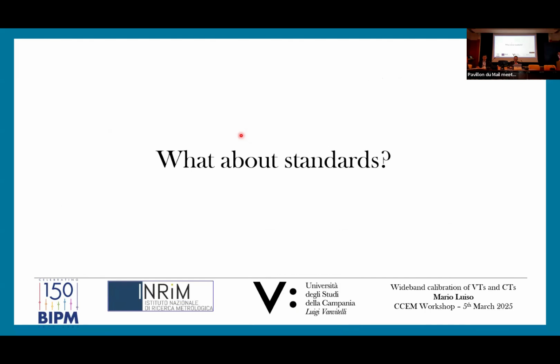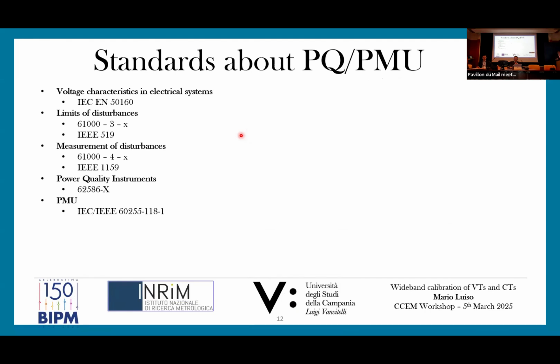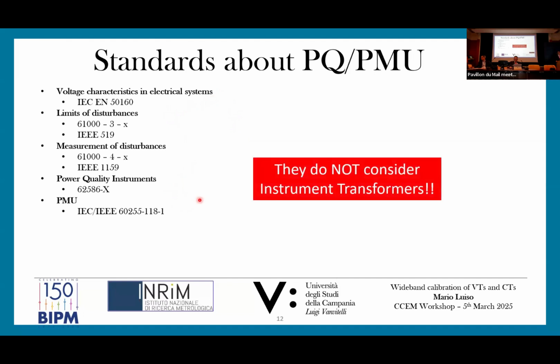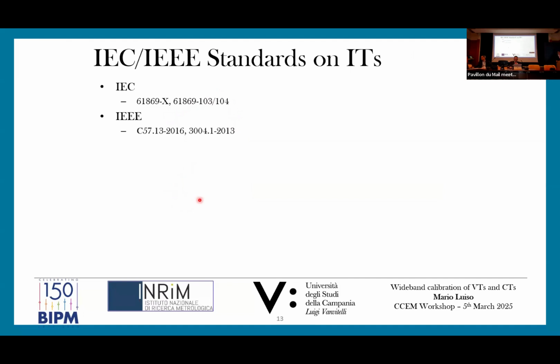But what about standards? We essentially have, related to this topic, two sets of standards. The first set regards the voltage characteristics in electrical systems, limits of disturbances, measurement of disturbances, characterization of power quality instruments, standards on phasor measurement units. All these standards do not consider the instrument transformers. On the other side, we have the standards on instrument transformer, mainly the family standard 61869 from the IEC.